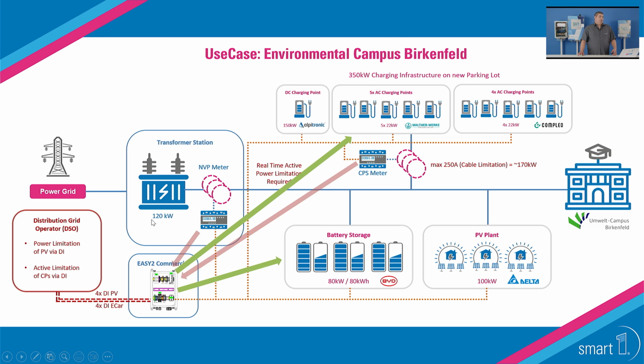We never draw or put more than 120 kilowatts into the grid, and the battery is used to support the charging infrastructure by providing power when cars are charging. In addition, it reads and monitors data from the PV plant for visualization, and at the end of the day, through control with the DSO, it also does the limitation.